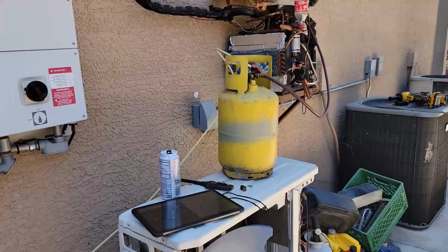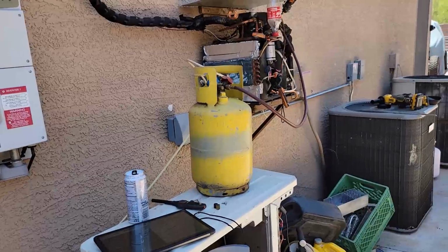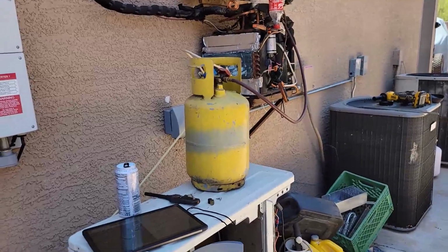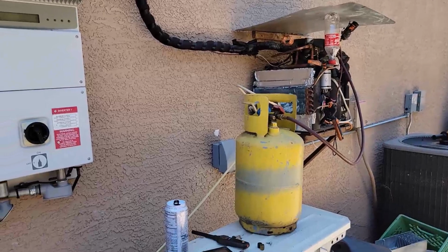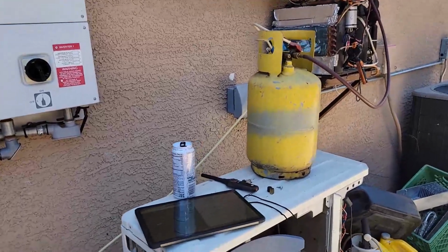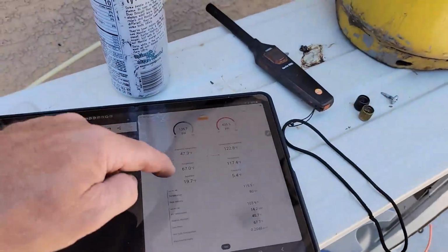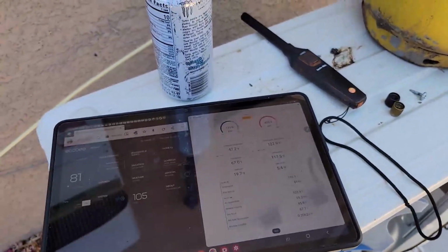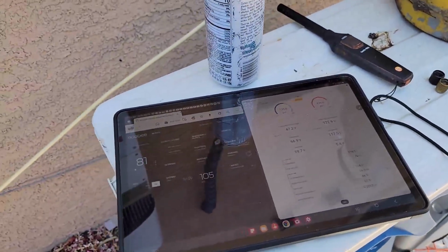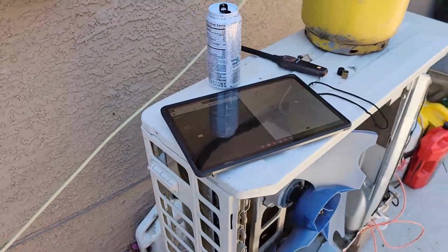in that space. Well, my phone just stopped recording on me, so I don't know where that cut out. Yeah, I have to empty some videos into the trash, and it happens. So I've been rambling too much. But I put just another little quick shot in there. Superheat's a little bit below 20. We're probably about there. So to end the video, let's go see what the temperature of the water tank and the temperature coming out of that high wall is. Of course, each time I open this door, I'm adding heat to the room.